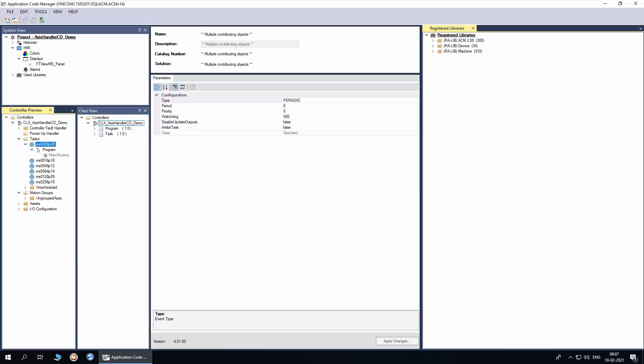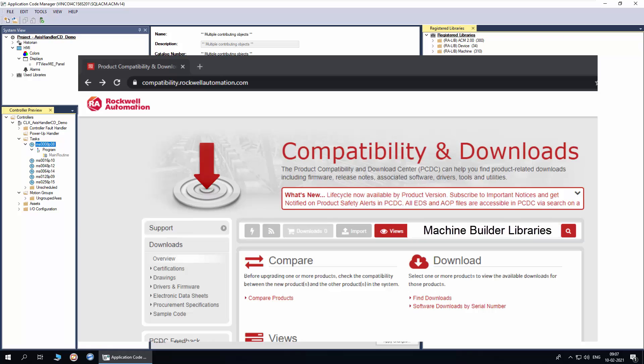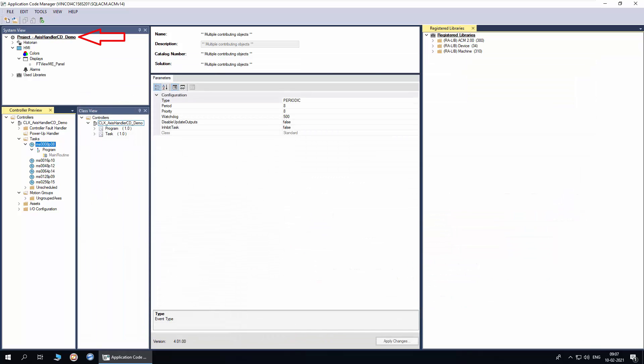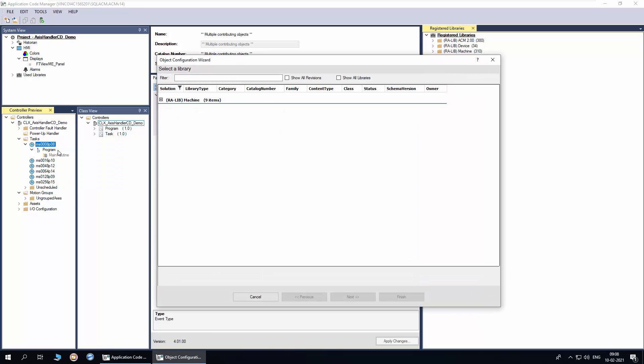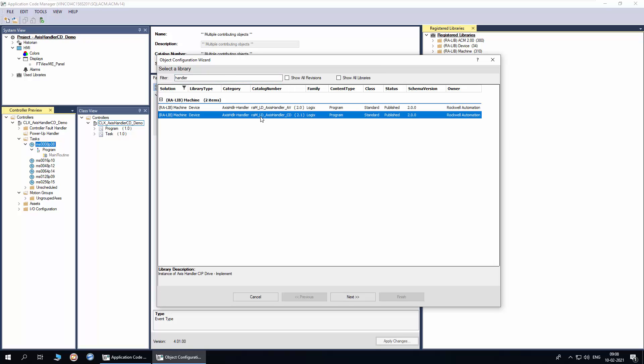In this section, I will demonstrate how to instantiate the axis handler CIP Drive object in Application Code Manager. The ACM already has machine and device library registered. You need to download the libraries from Rockwell Automation's Product Compatibility and Download Center page. I have already created a project, added a controller and display. I have also added a program in which we will add the axis handler CIP Drive implementation object. To add, right-click on the task and click add new. In the filter, enter handler. Select the axis handler CIP Drive implement object and click next.